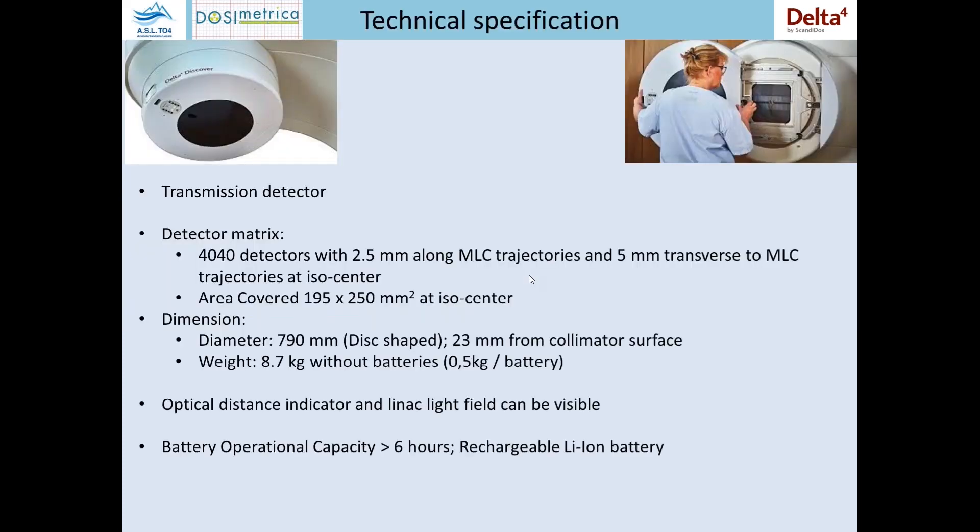So what is Discover? It is a transmission detector formed by 4040 detectors separated by 2.5 millimeters along the MLC trajectories and 5 millimeters in the transverse direction. It covers a total area of 195 millimeters by 250 square millimeters. This disc has a dimension of about 790 millimeters and 23 millimeters of thickness and it weighs more or less nine kilos.